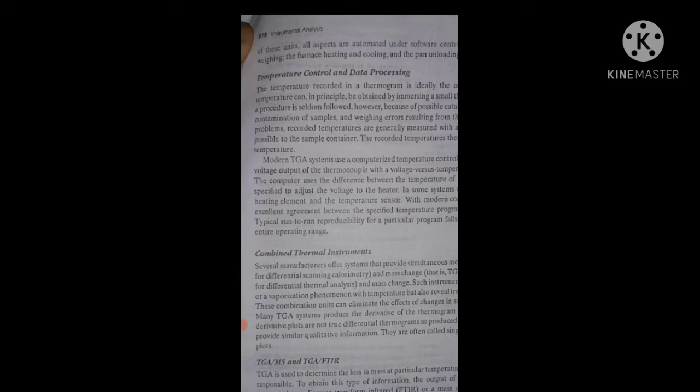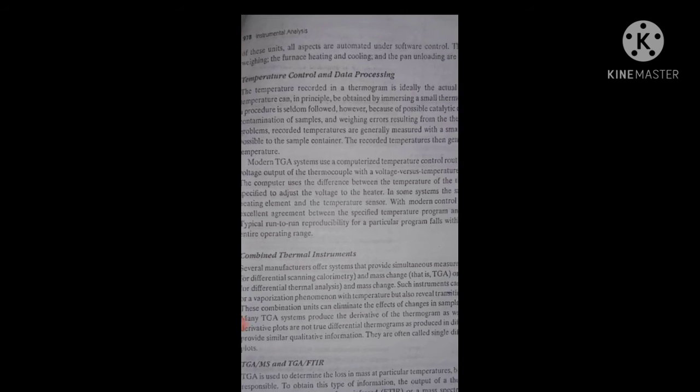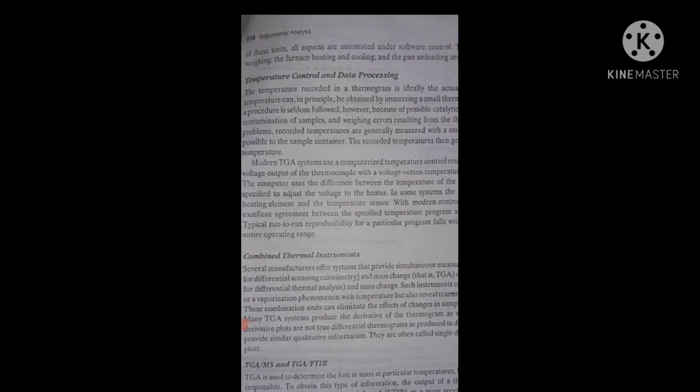This will affect three things: one, it can contaminate the sample; second, there may be catalytic decomposition of the sample. Thermocouples are made of bimetallic strips, so they act as catalysts. The third one is there may be weighing error resulting from the thermocouples.